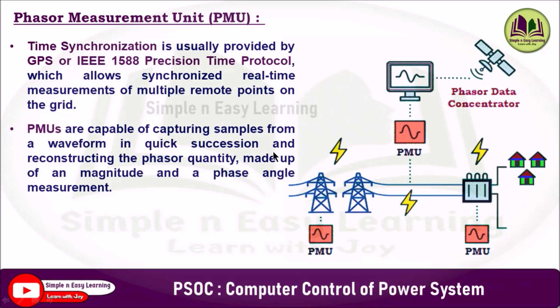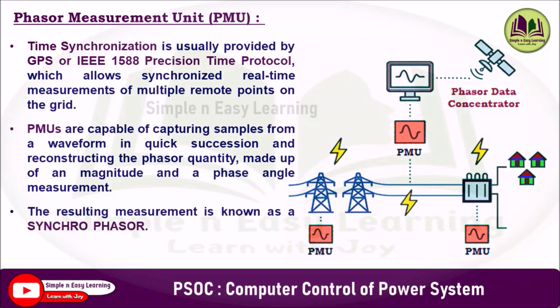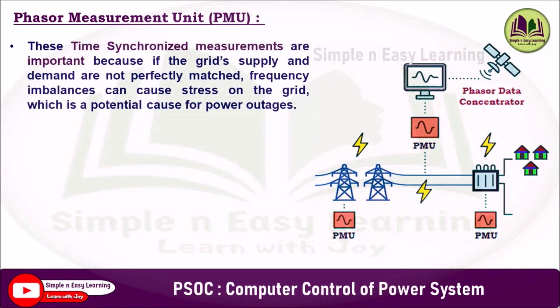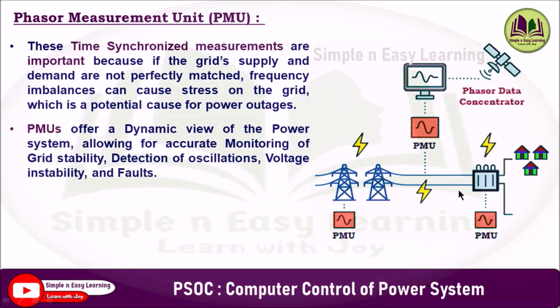Phasor measurement units are capable of capturing samples from a waveform in quick succession and reconstructing the phasor quantity, made up of a magnitude and a phase angle measurement. They take nearly 120 samples per second, and the resulting measurement is known as a synchrophasor. These time-synchronized measurements are important because if the grid supply and demand are not perfectly matched, frequency imbalances can cause stress on the grid, potentially causing power outages.